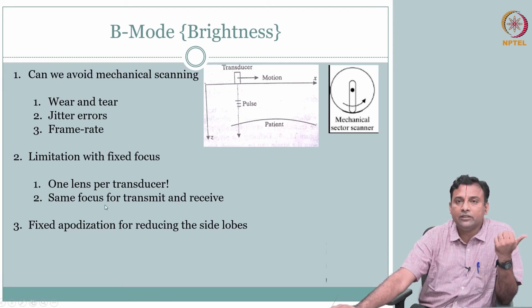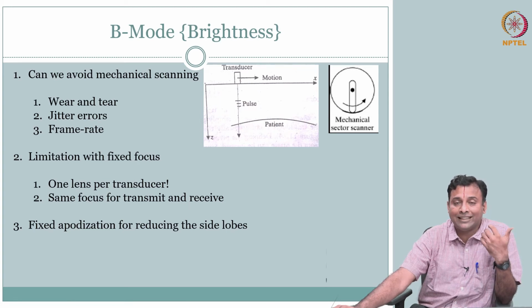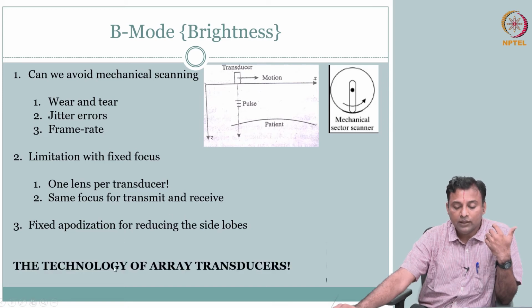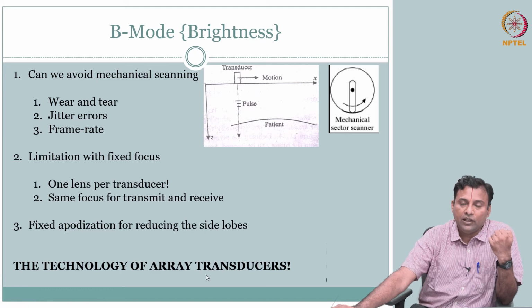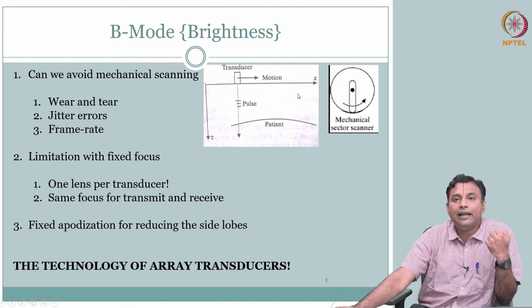Overcoming these limitations got addressed, and a lot of migration, transition, and development in ultrasound as we see today took place because of the advent of the array transducers. What do we mean by array transducers? Instead of one element that you have here, you have multiple elements, right.